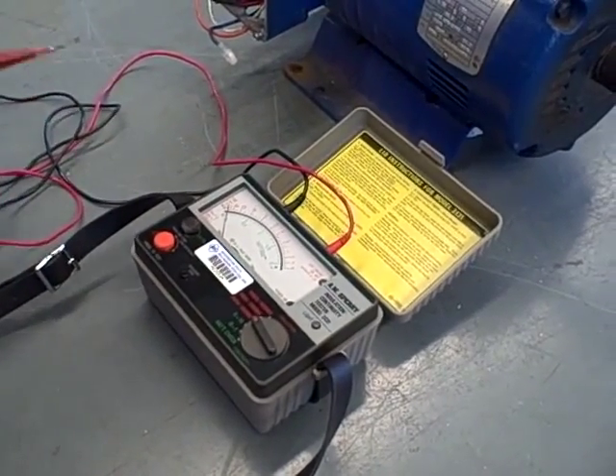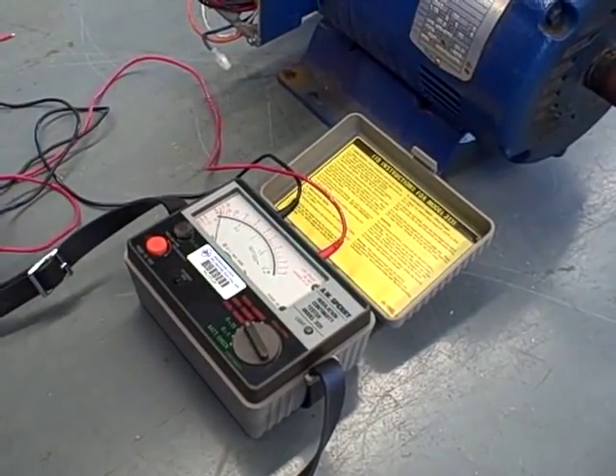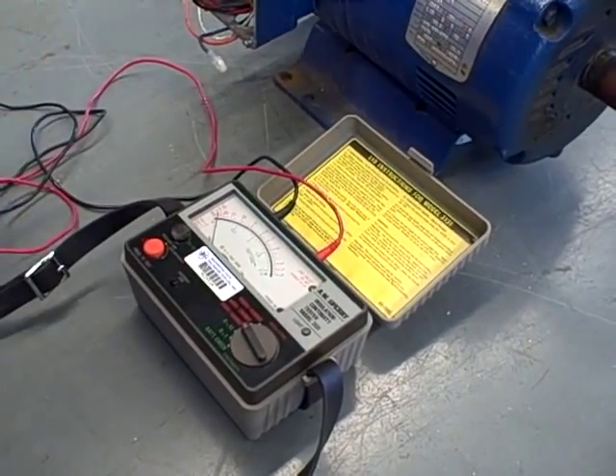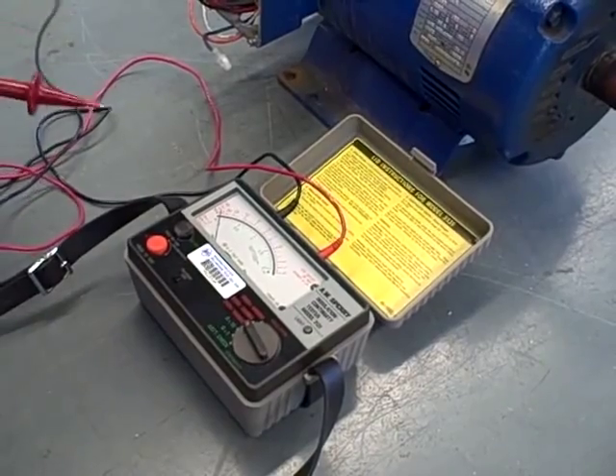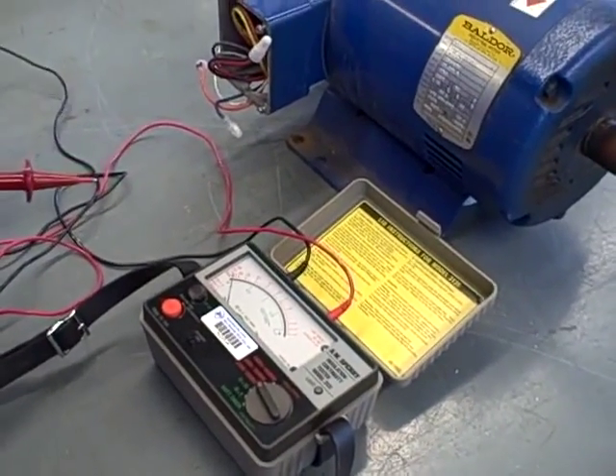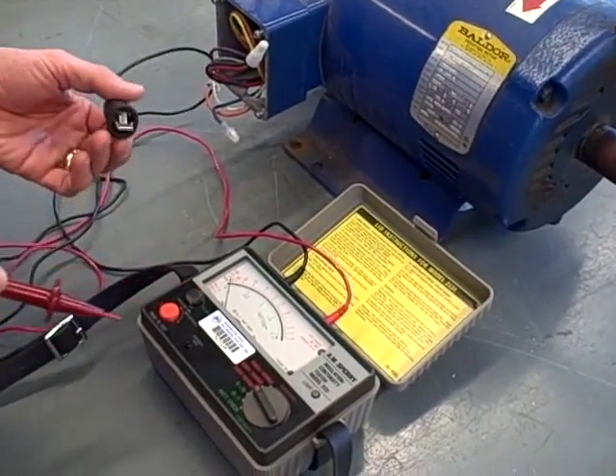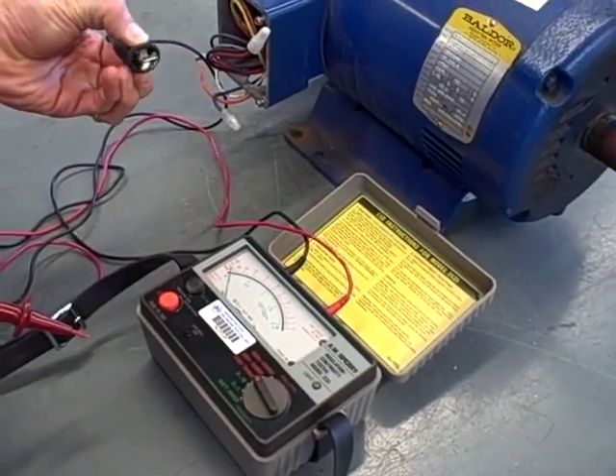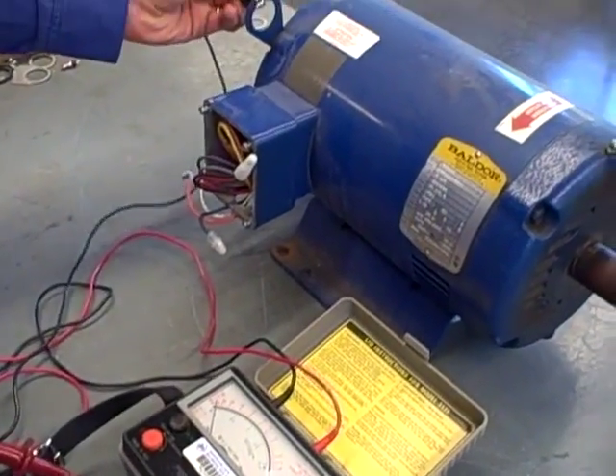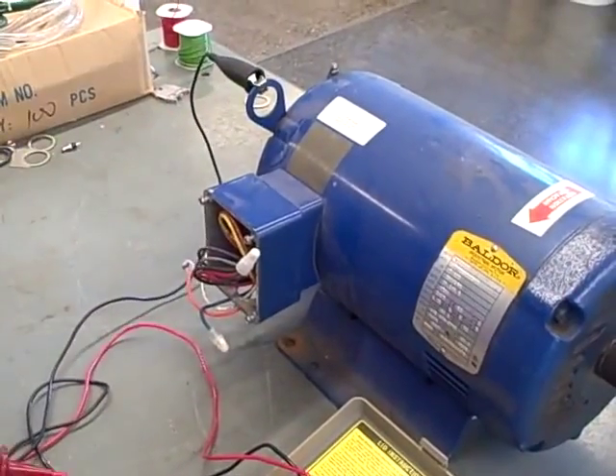I'm going to illustrate this using this Baldor 7.5 horsepower motor. This is a failed motor that was pulled out of service because it has a ground fault in one of the windings. I want to demonstrate how we can prove that with our Megger, our insulation tester. First, I'm going to take the ground clip and move that to an area on the motor itself where I get a good solid ground.